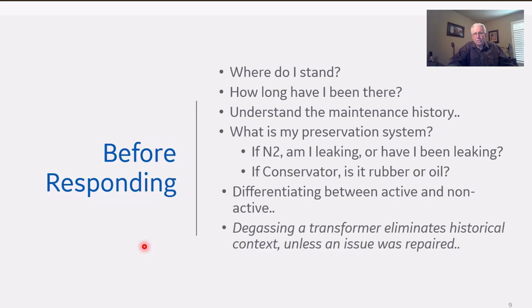Degassing a transformer - I've seen this over and over, more so in some areas than others, where gassing develops in a transformer. One of the things people might do is take a transformer out of service, degas it, put it back in, and you know what's going to happen: it's going to start gassing again because it never stopped gassing. We just eliminated that history for the moment. So degassing a transformer fixes nothing.